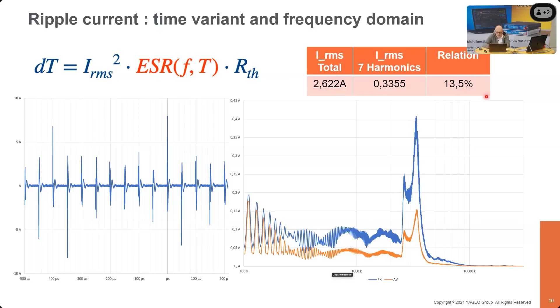But look at this relation: if I take all the higher harmonics, the whole frequency spectrum, I end up with a total current through the capacitor of 2.622 amps, while what was typically done in the past, using only 7 harmonics, gives 335 milliamps—a huge difference. This is one reason why we need to get better at simulation and getting the ESR correct across the whole frequency range. That's the topic.